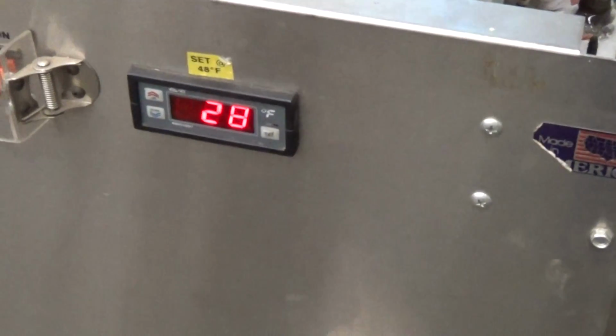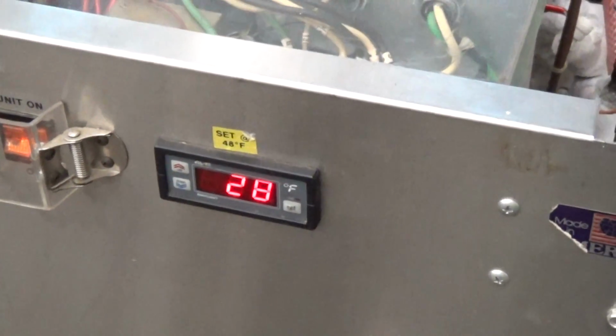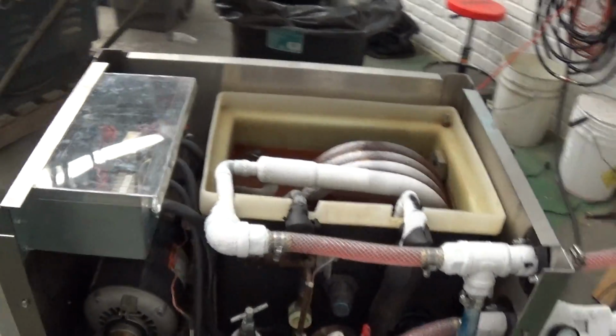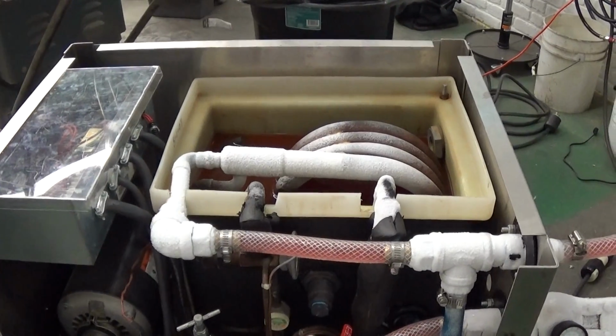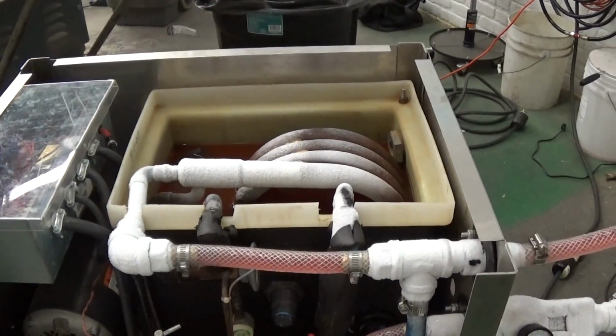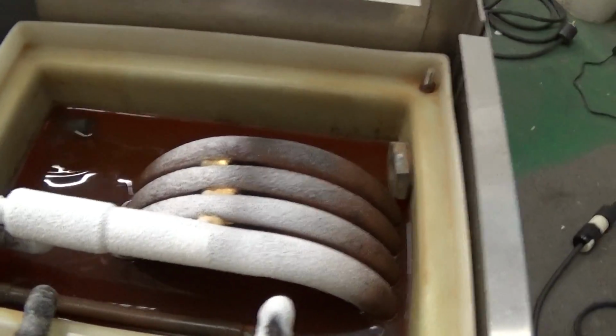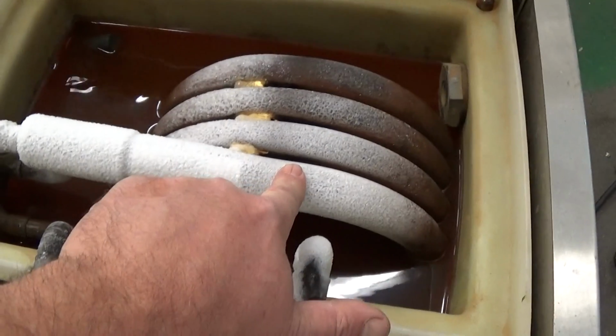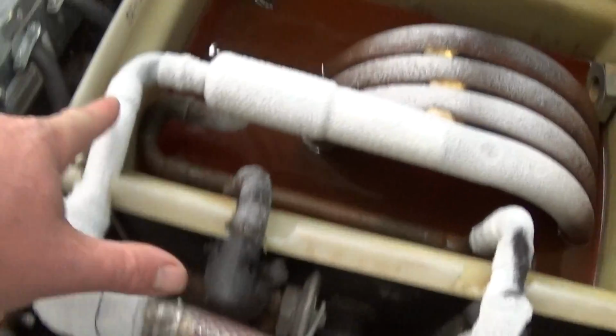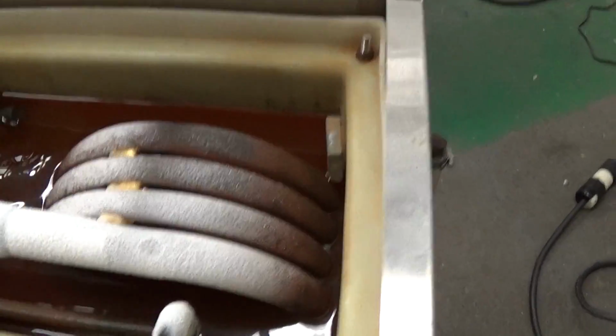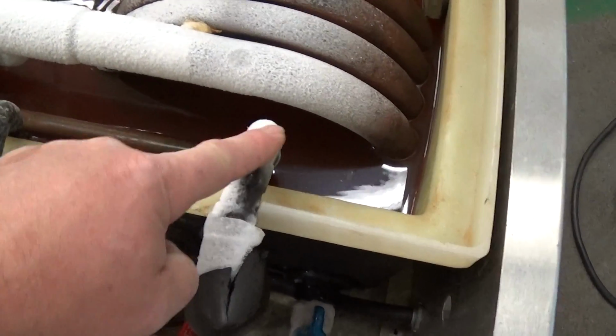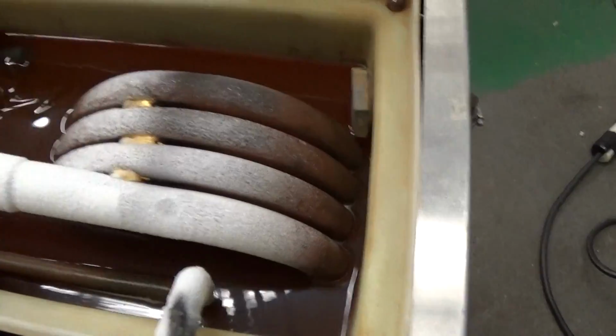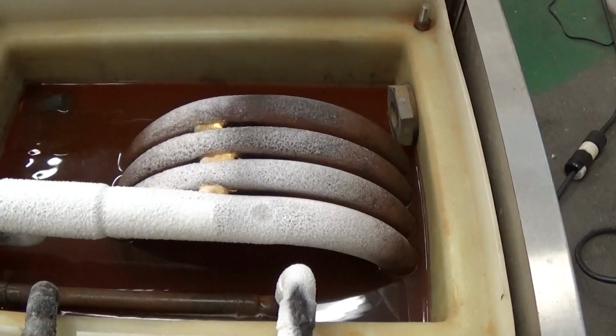And you can hear the compressor just turned off, and you can hear the pump still running. And it'll chill down to 28 Fahrenheit until the temperature comes back up. Again, I haven't touched this since Friday afternoon, so about 60 hours straight of runtime without touching it. Again, this is our little reservoir, and this is the refrigerant to fluid heat exchanger here from your process. It comes in and through this heat exchanger, and then on the other side of the heat exchanger with an internal piping, I guess you could say, is where the refrigerant to fluid heat exchanging is taking place.